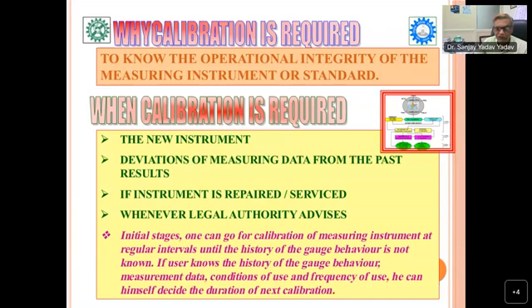In the initial stages, one can go for calibration of the measuring instrument at regular intervals until the history of the gauge behavior is known. If the user knows the history of the gauge behavior, measurement data, and condition of use, meaning whether measurements are performed in a laboratory or in a workshop, these are conditions you have to remember. He can himself decide the duration of the next calibration, because ISO 17025 itself says that it is user dependent. Already one document is published by OIML, I think D8 or something, I don't remember exactly, D8 probably Ashutosh ji might be remembering. This calibration interval is clearly mentioned there, with all conditions. It's a small document, maybe 5-6 pages.